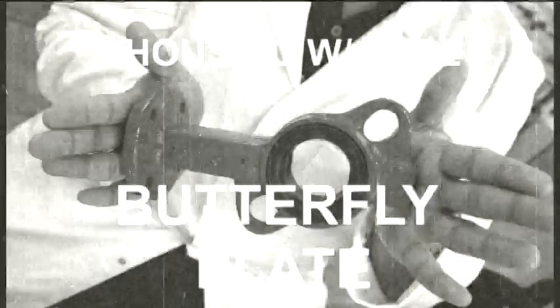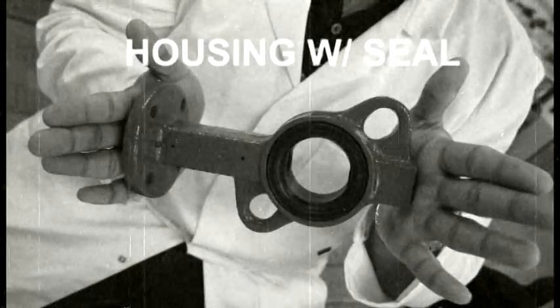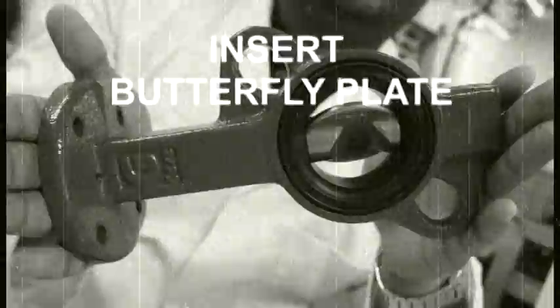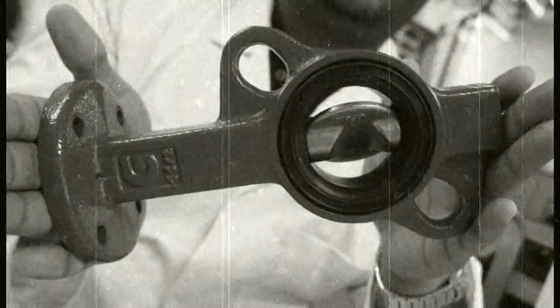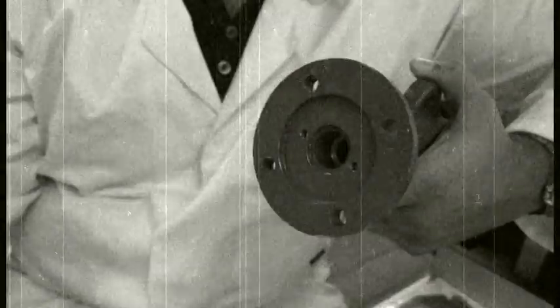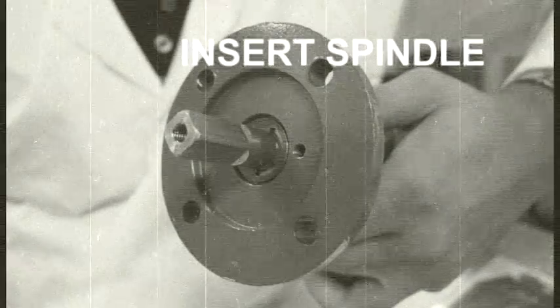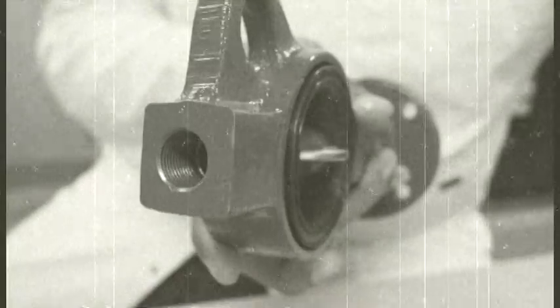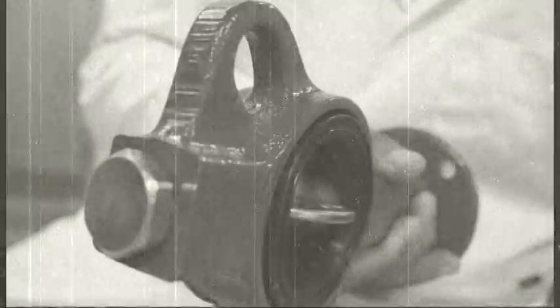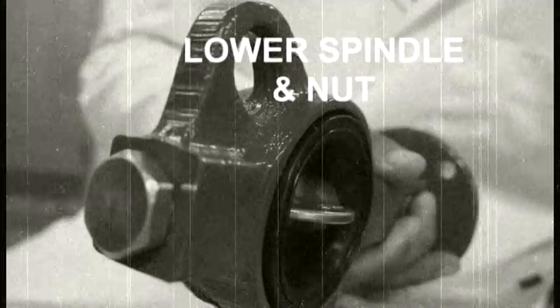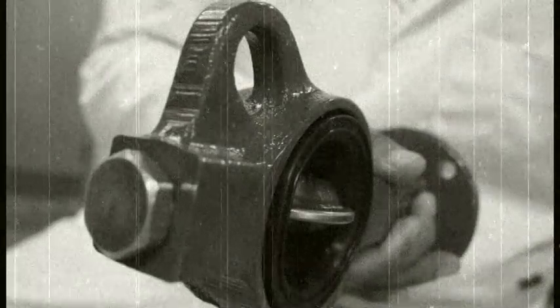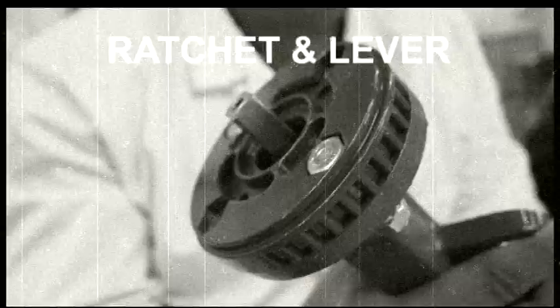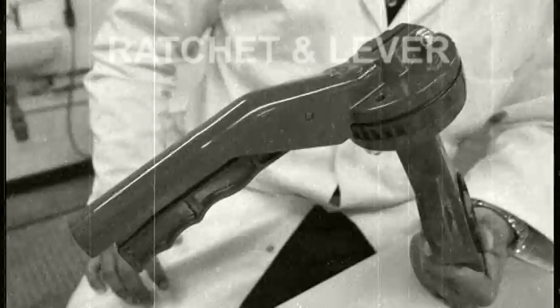Here in the first picture we can see the bare housing of the butterfly valve with the black rubber seal. Then we must insert the actual butterfly into the rubber seal. This is the top side of the housing. We insert the upper spindle itself. This is now a view from the other side of the housing. From here we insert the lower spindle and enclose it with a plug screw and a washer. We then attach the ratchet disc, on top of which the handle is placed.